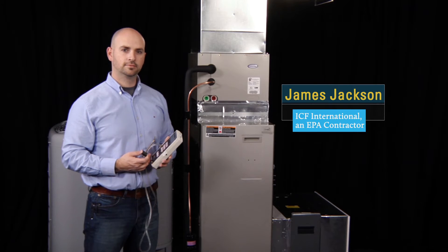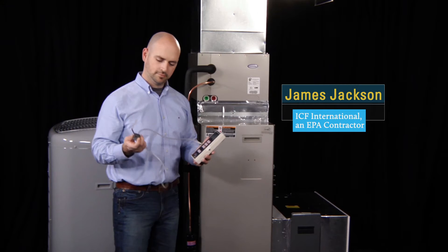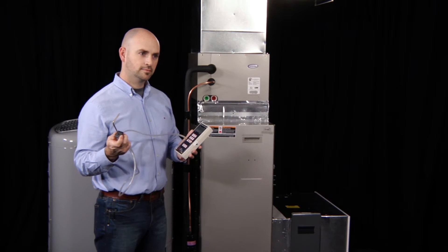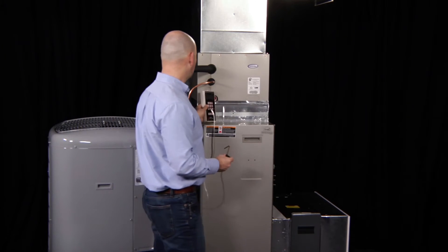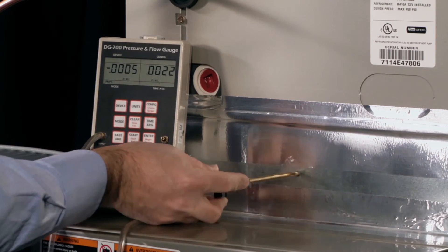Now, James has already connected the tubing to the static pressure probe and the manometer and turned on the HVAC system. To take a reading, all he has to do now is insert the static pressure probe into the hole, officially called a test port, and read the resulting pressure on the manometer.